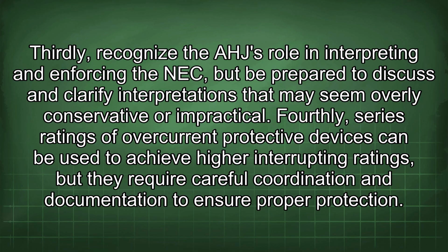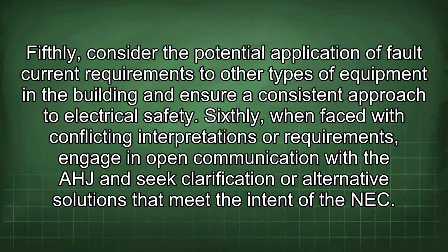Fourthly, series ratings of overcurrent protective devices can be used to achieve higher interrupting ratings, but they require careful coordination and documentation to ensure proper protection. Fifthly, consider the potential application of fault current requirements to other types of equipment in the building and ensure a consistent approach to electrical safety. Sixthly, when faced with conflicting interpretations or requirements, engage in open communication with the AHJ and seek clarification or alternative solutions that meet the intent of the NEC.